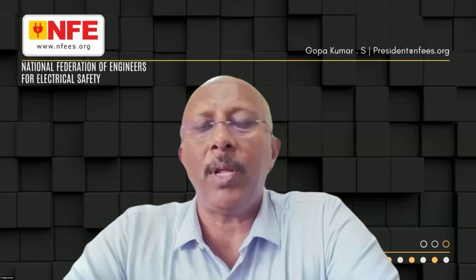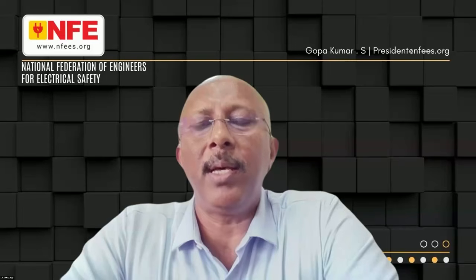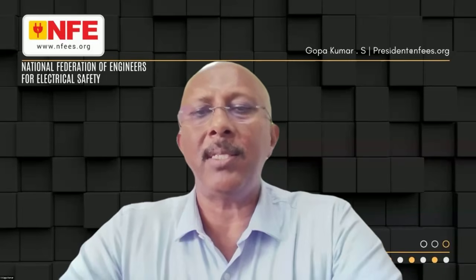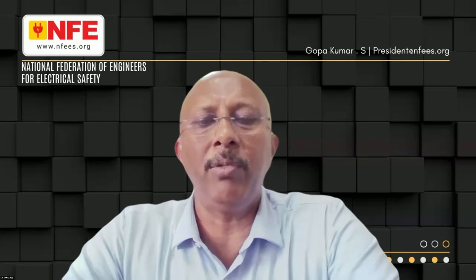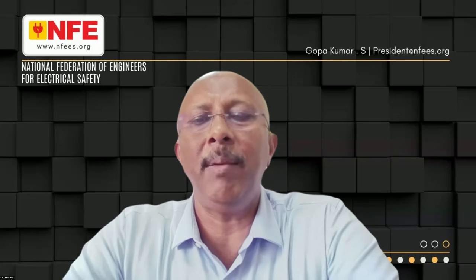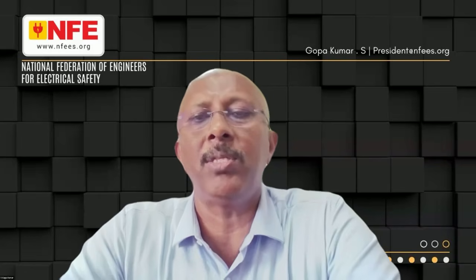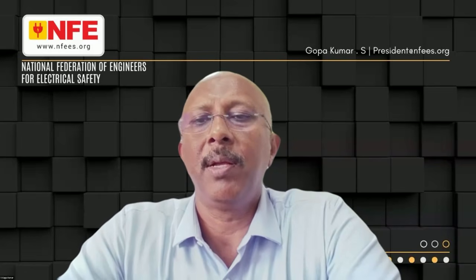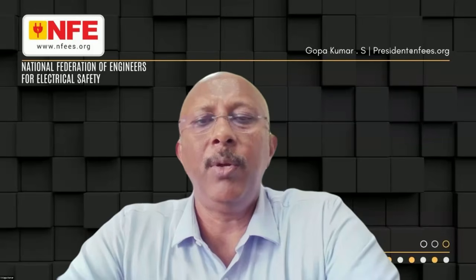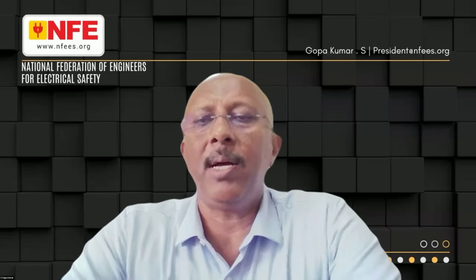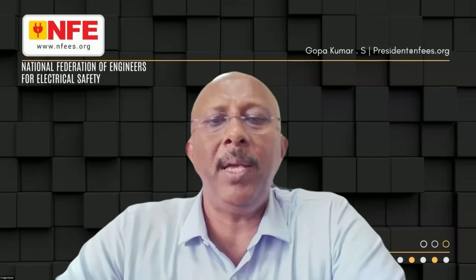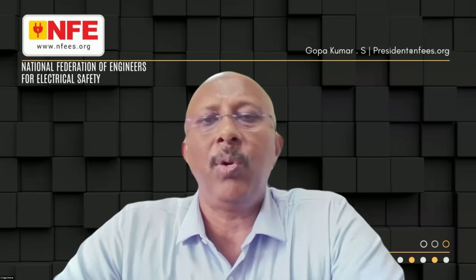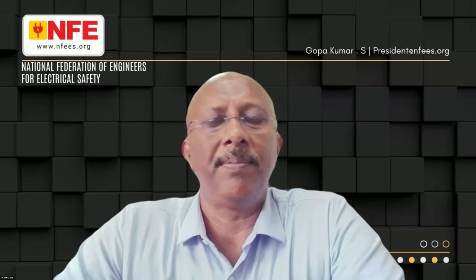If you are putting a 30 milliampere RCCB for fault protection for a group of electrical equipment or biomedical equipment together, for example the LED lights, computers, all these things together produce a leakage current of more than 9 or 10 milliampere, which will create nuisance tripping of the RCCB. Because there is inherent leakage current for the equipment, which is not a fault. Due to inherent leakage current added together, the device starts tripping, which will be another hazard. So all these things need to be taken into account.